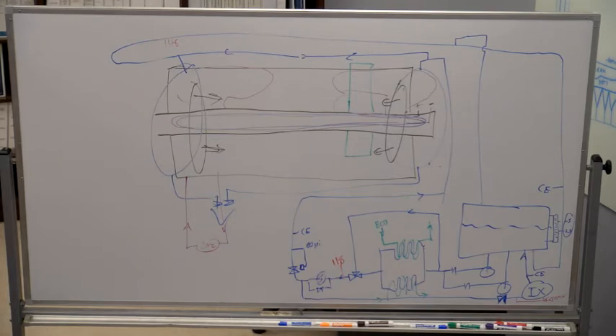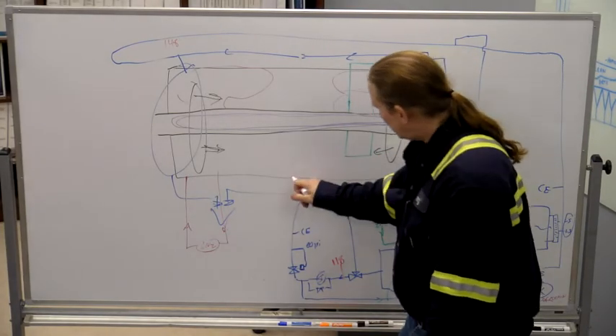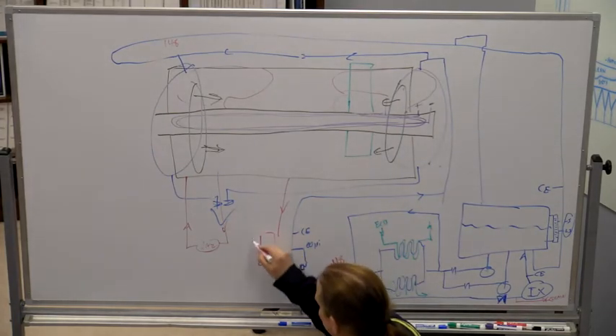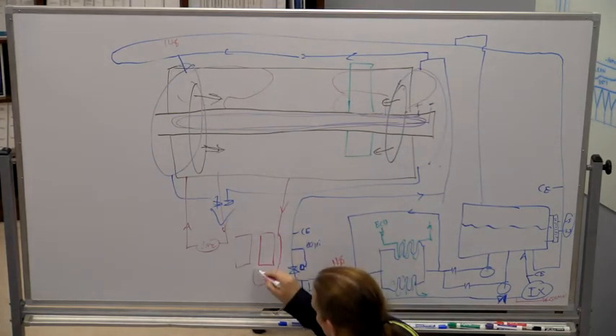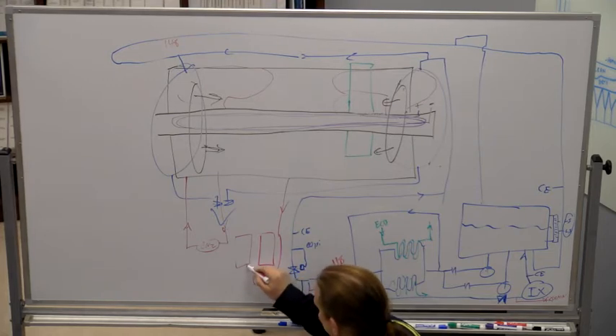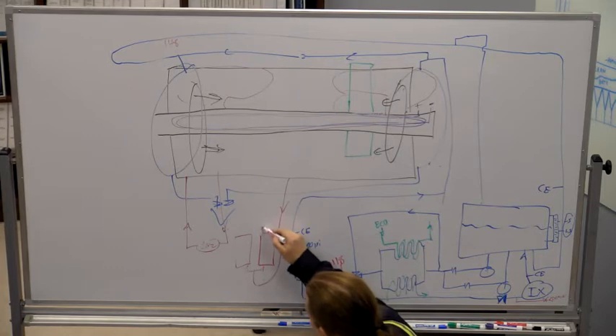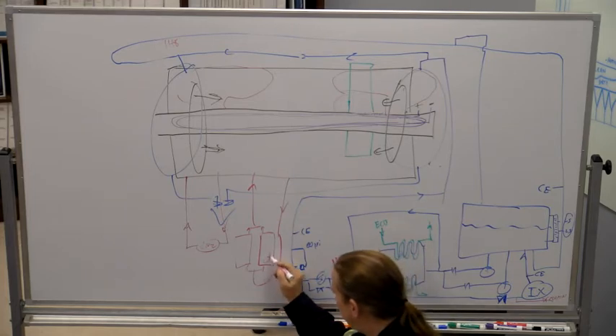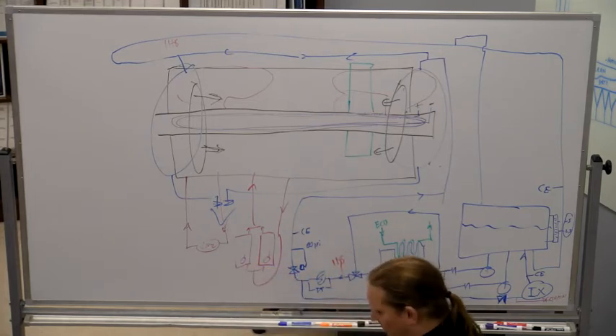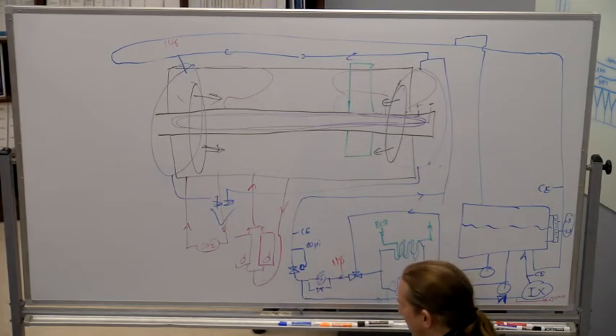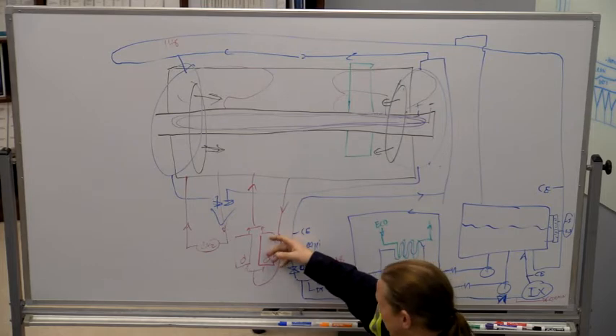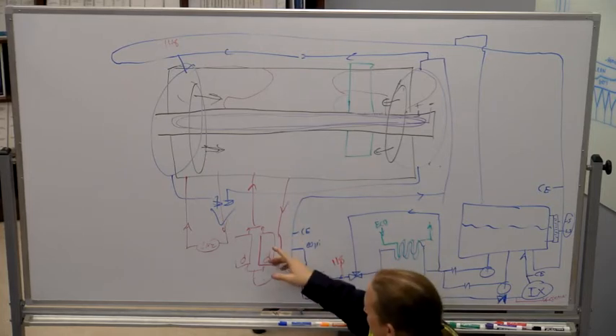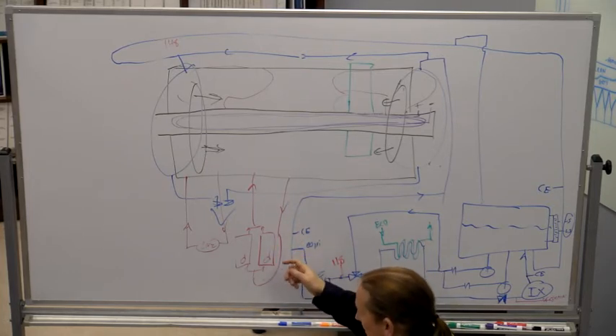Alright. There is a hydrogen dryer. So the hydrogen dryer pulls hydrogen down, and you've got two towers of desiccant. One tower is in service, and the other is regenerating. Each tower has a blower built into it. The desiccant absorbs the moisture, and then when the dew point on the outside starts to go up, then it swaps towers.